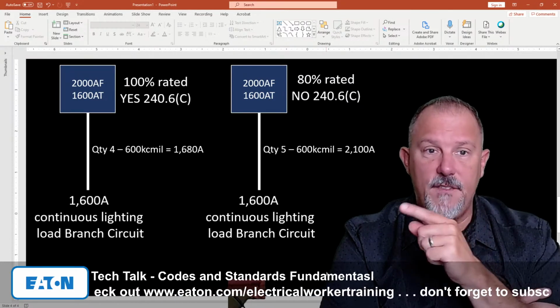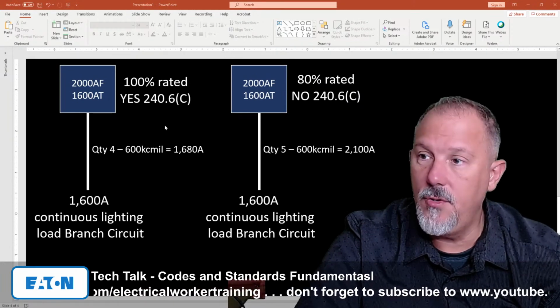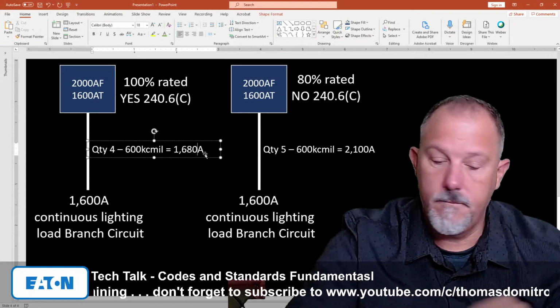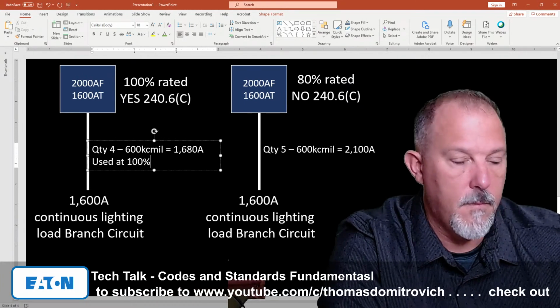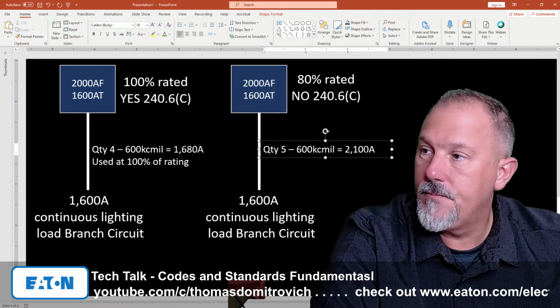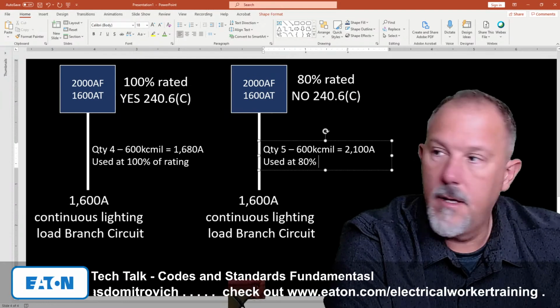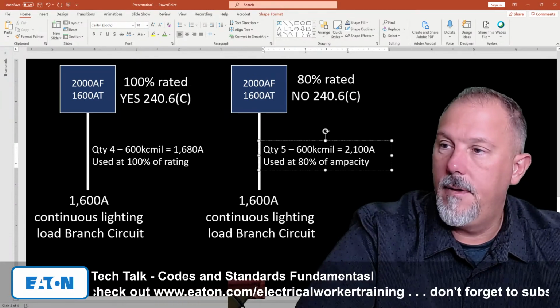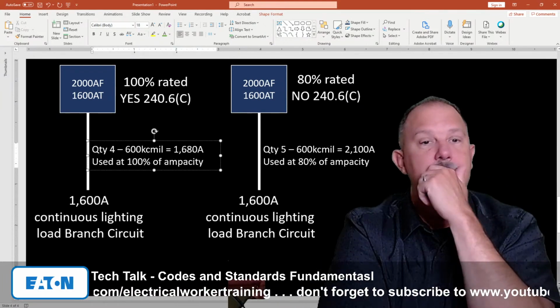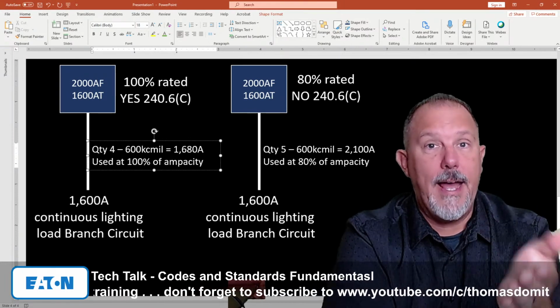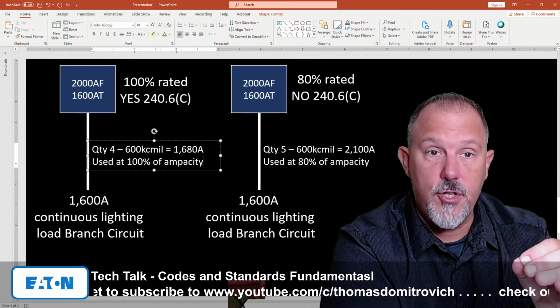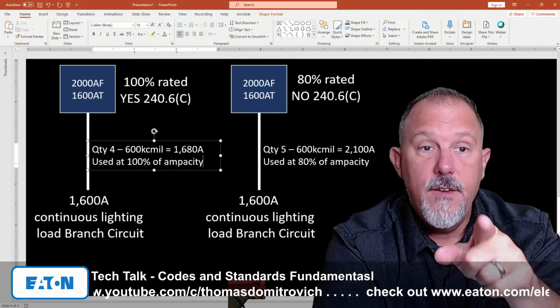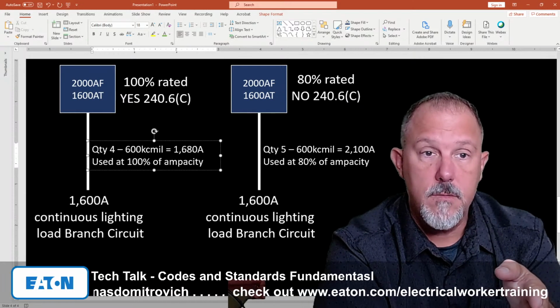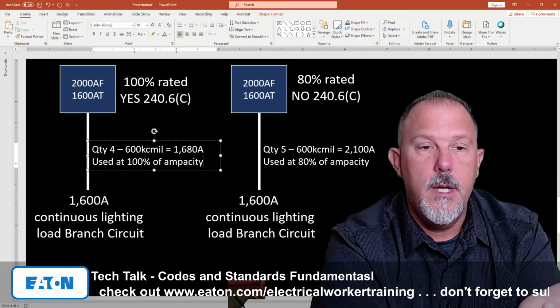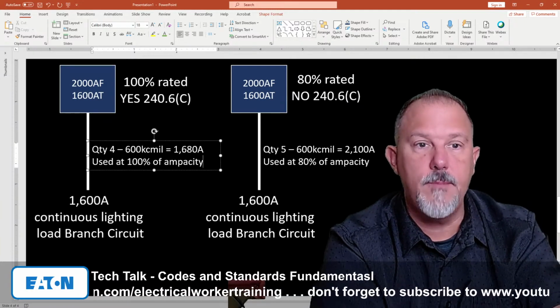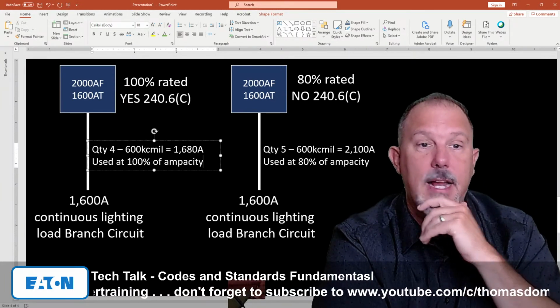Yes, Felix, on the left, these conductors are being used at 100% of their rating. And over here on the right, I'm going to say ampacity. I'm using the breaker at 100% of its rating because it is technically per 240.6c rated at 1600 amps. I can use 4 600 kcmils up to 1600 amps, right? At their ampacity, because if I go to 1680, ultimately it's going to trip. But I could use those 4 600 kcmils at 1600 amps. The breaker and the equipment is 100% rated, and I have 1600 amps worth of continuous load.